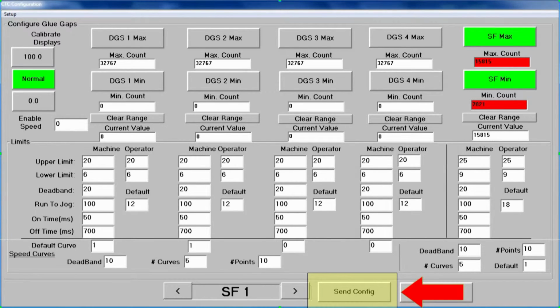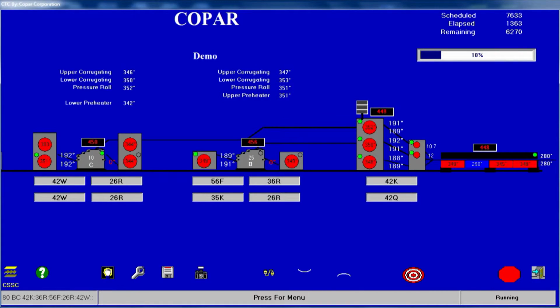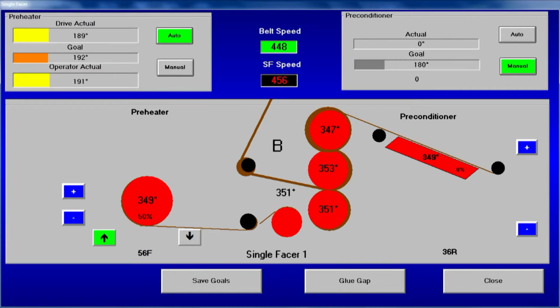When done, press the Send Config button on the bottom of the screen to send the parameters to the PLC. It's a good idea to check the Copar screen to make sure the values were correctly entered. Since the gap is currently at the upper limit, 25 thousandths in this example, we can see if Copar displays 25 thousandths. The value is displayed in the overview screen or by selecting the single facer detail screen.